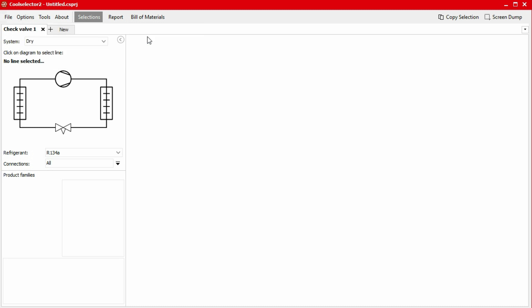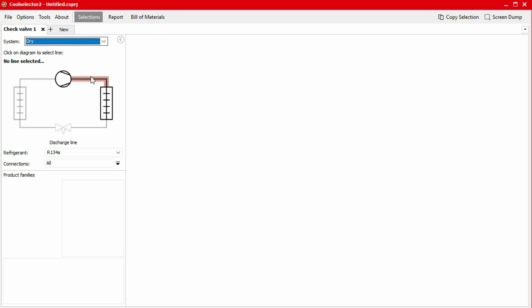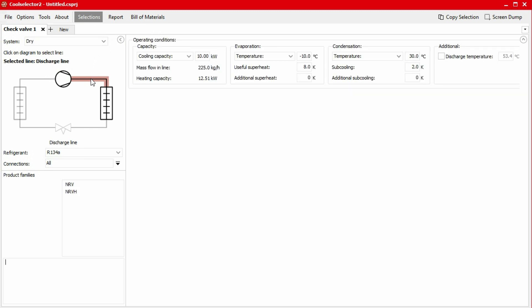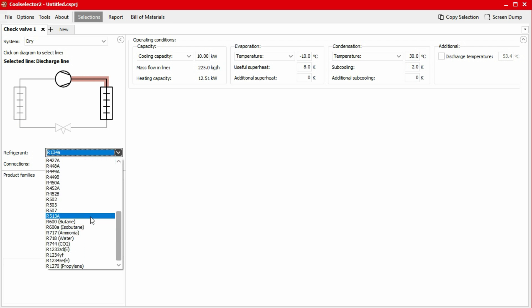We begin in the top left-hand panel by first selecting the system type. In this case, we'll use a dry system. We can then select where in the system the valve will be installed using the system schematic. In this case, we require a check valve for the discharge line. Next, we choose which refrigerant our system is using — we'll choose R513A from the drop-down menu.